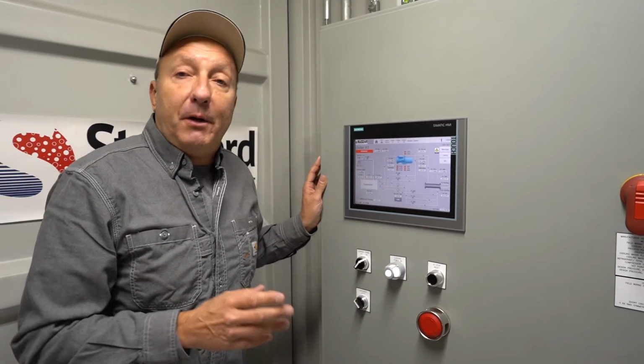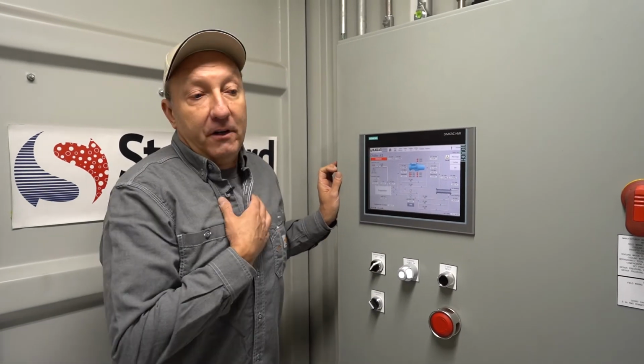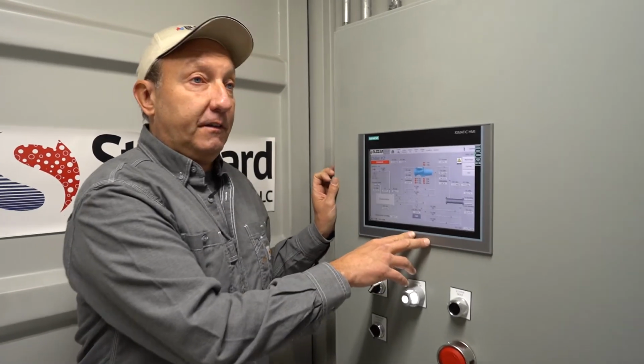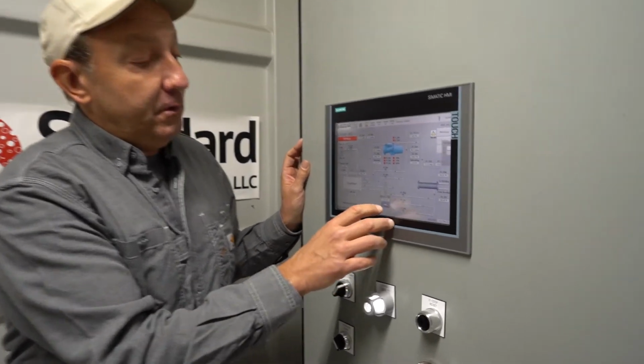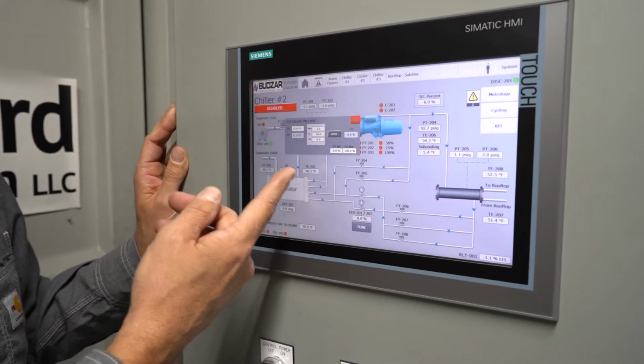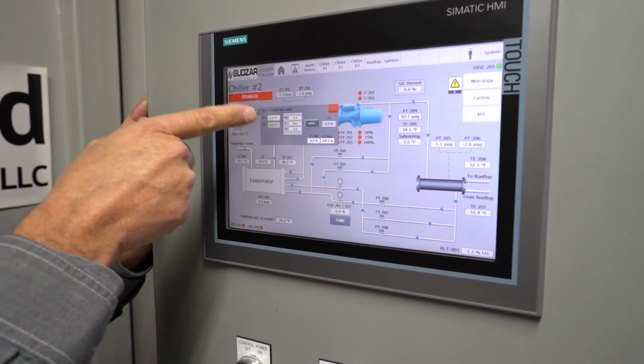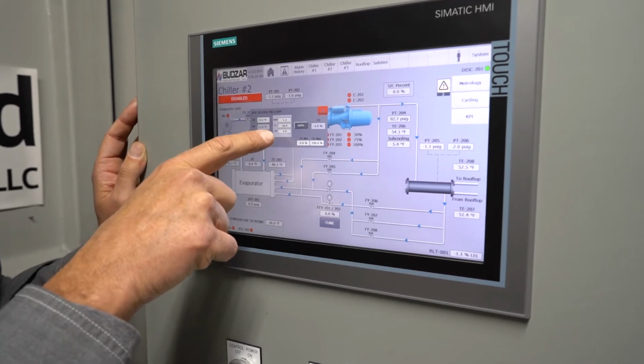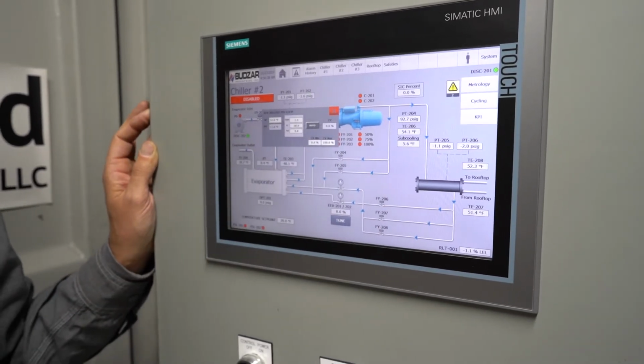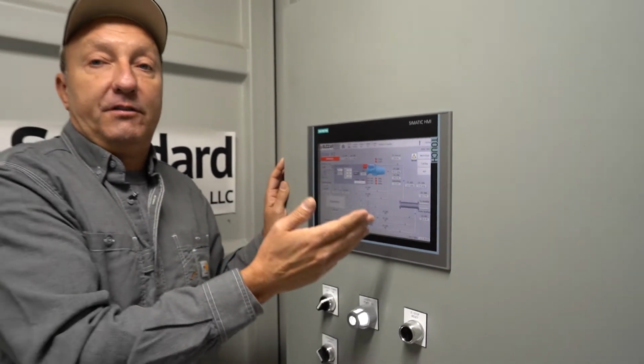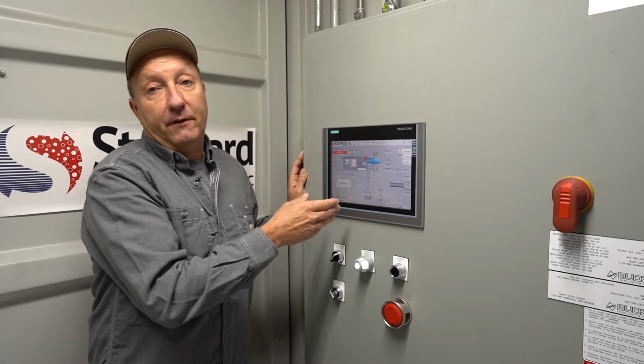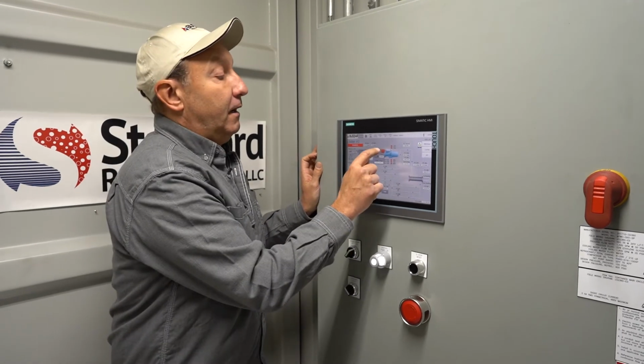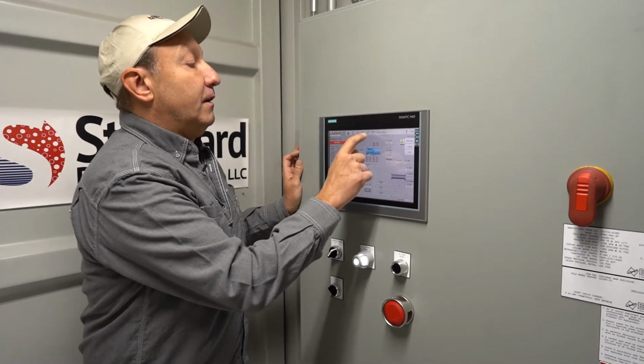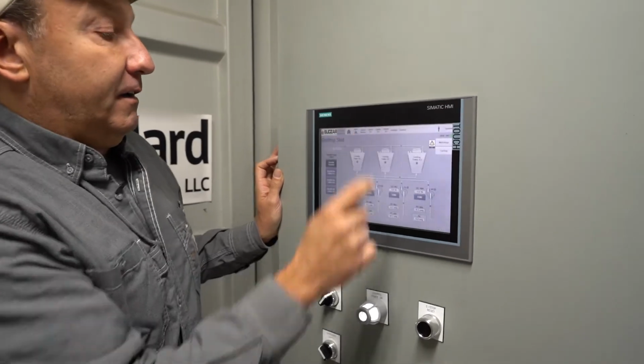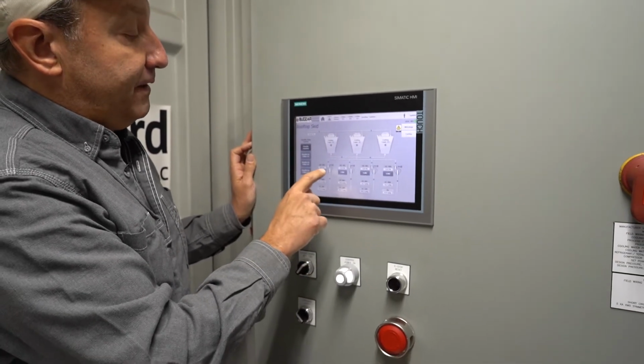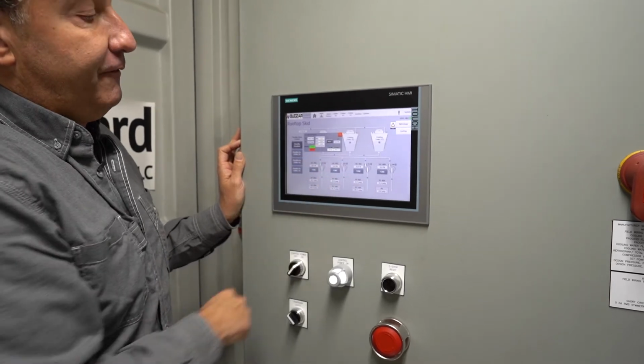Okay, now for troubleshooting purposes, or I'll be utilizing these buttons here soon when we run the system and do further tuning, but I can tune, for example, the electronic expansion valve. It has our superheat set point of 12 degrees Fahrenheit, and this is my PID tuning block, and I also have a manual function. I can open and close this valve to any position I want based on a percentage on the 4 to 20 milliamp loop. It's also programmed pretty creatively.